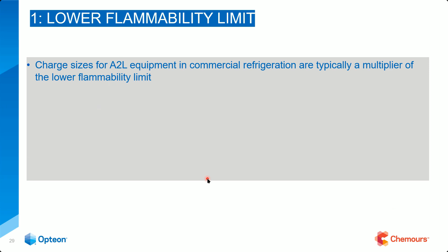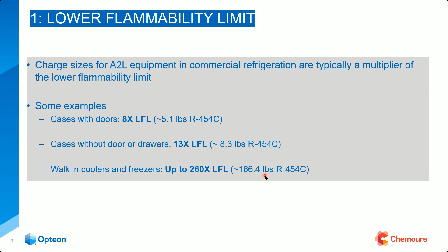So what are the requirements? Some examples: for cases with doors and drawers, it's 8 times LFL. So in the case of 454C, that would be about 5.1 pounds of 454C. Cases without doors or drawers will have 13 times LFL, somewhere around 8.3 pounds for 454C. Now, walk-in coolers are up to 260 times LFL, and for 454C, that's approximately 166.4 pounds. If you don't know what that little squiggly mark means, it simply means somewhere thereabouts, or nominal, if you will.